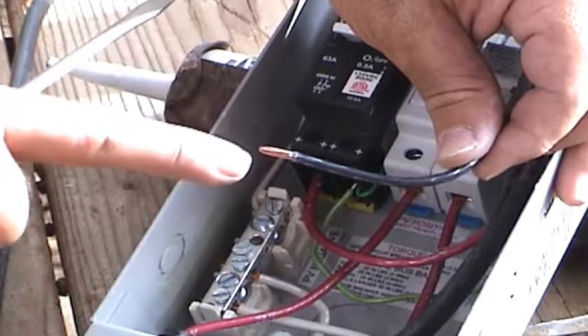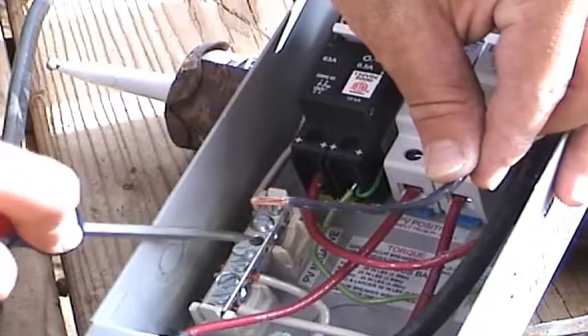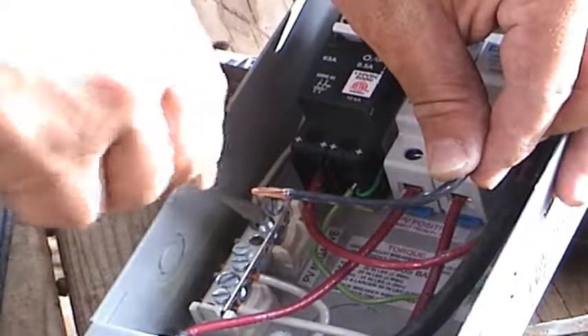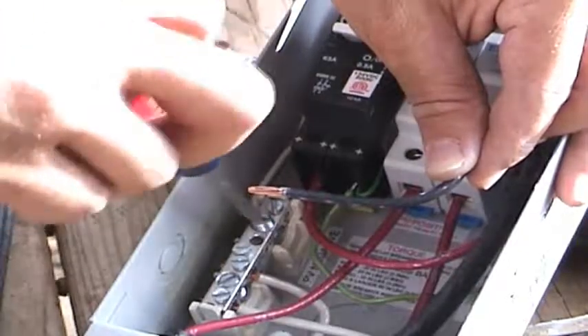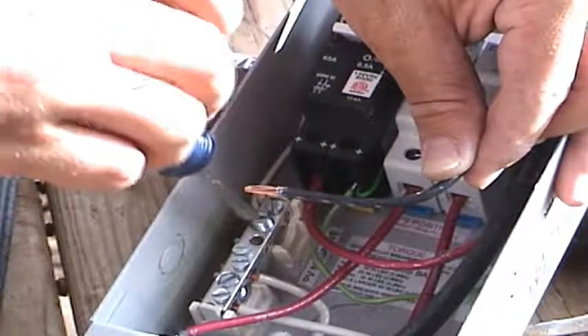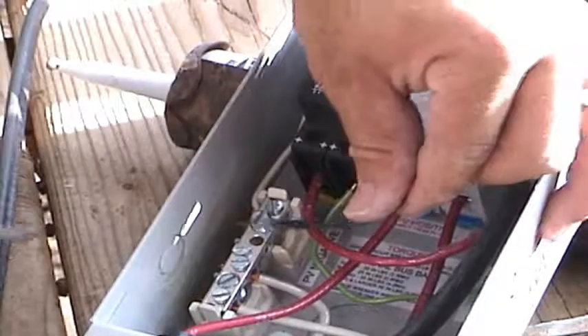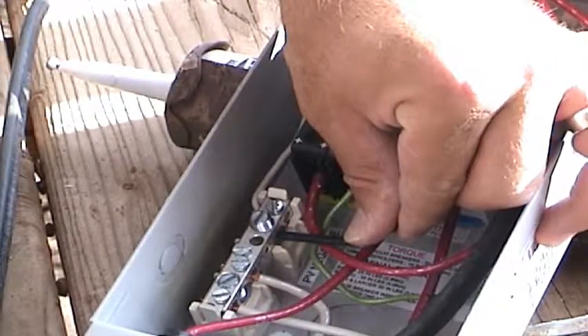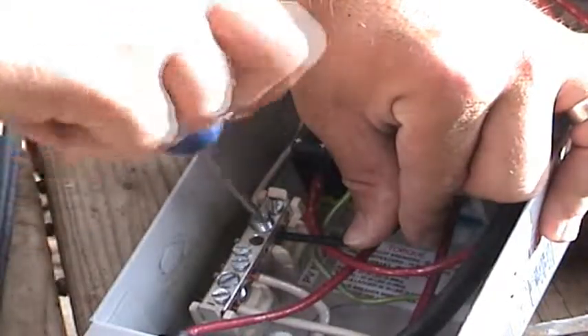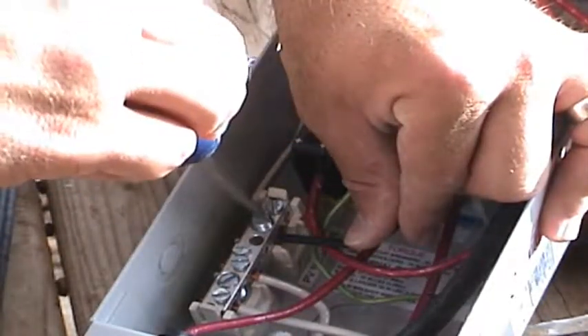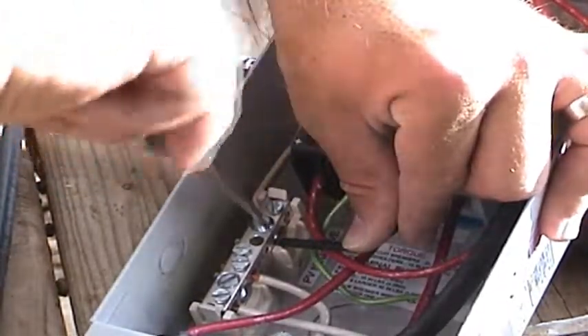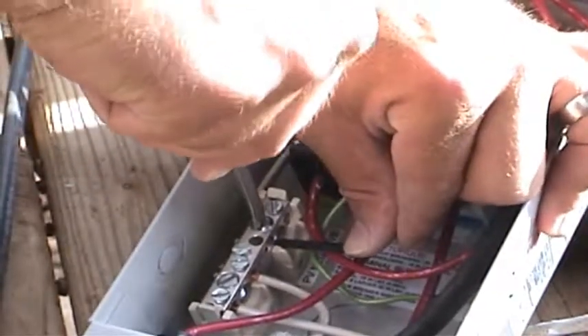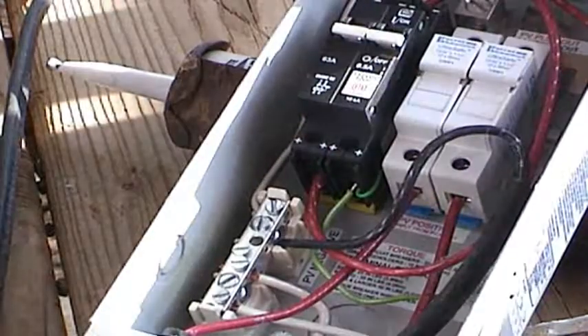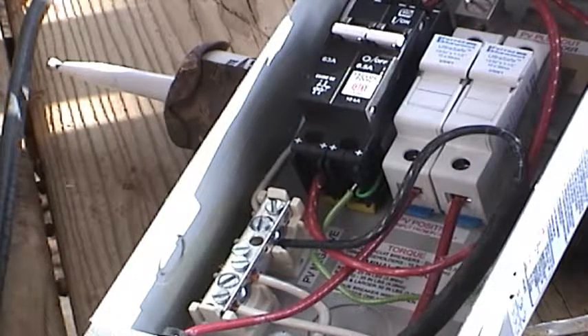Now let's connect the black wire from the outdoor cable to the PV negative bus bar. Let's go ahead and loosen one of the screws from the larger holes on the PV negative bus bar. And let's insert the black wire and tighten the screw as tight as you can go. Okay, our combiner box is now ready to mount next to our solar panels.